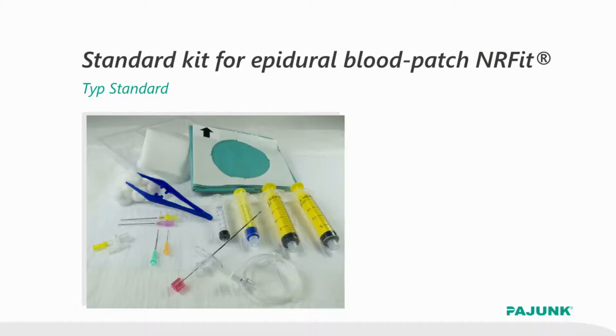How do you want to deal with blood patches? Aspiration of blood is an intravascular application that will remain a Luer application. However, the injection is a neural application. We offer a blood patch set that covers both ends. This set features a connector tube through which the blood may be transferred from Luer to NRFit.